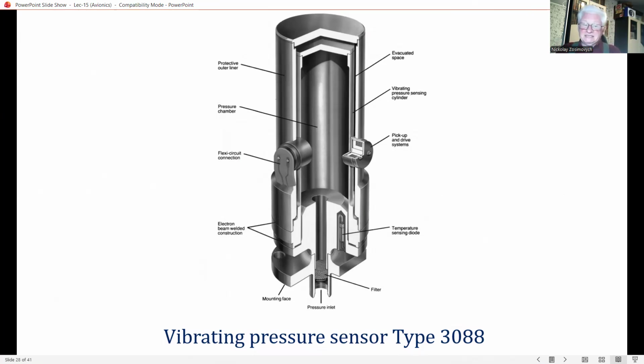And this type of sensor is extremely rugged. The very high Q of the cylinder confers very low susceptibility to vibration and shock, and the absence of moving parts enables it to withstand a very high acceleration environment. The inherent simplicity and very low power consumption enables a very high reliability to be achieved, together with very high accuracy and long-term stability.